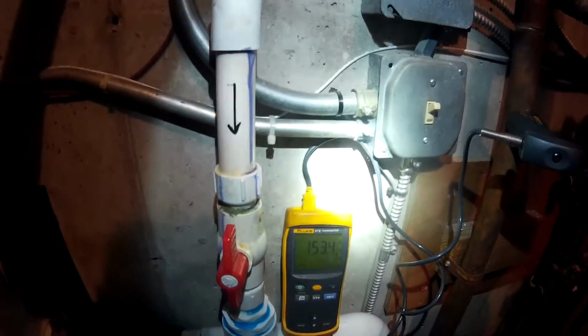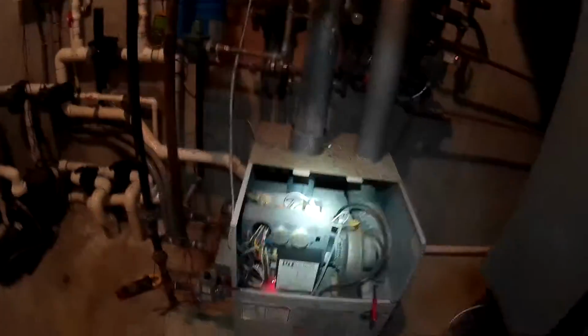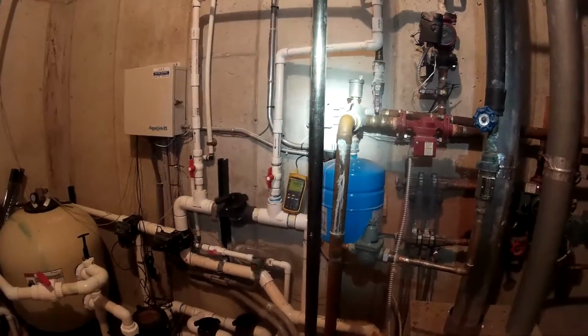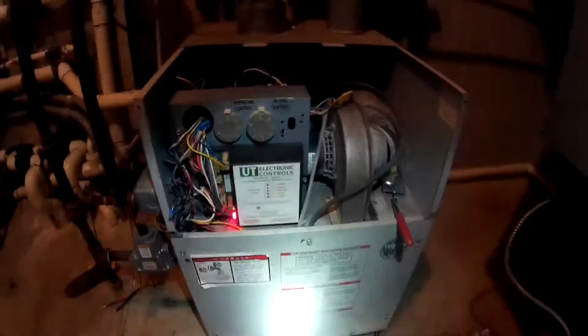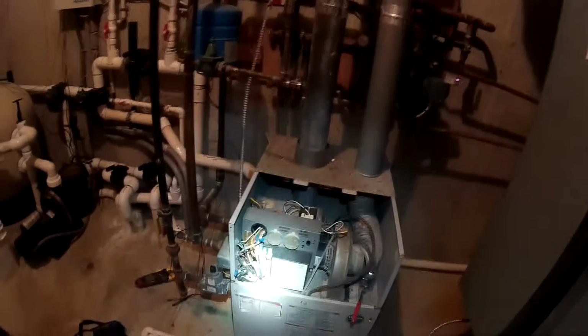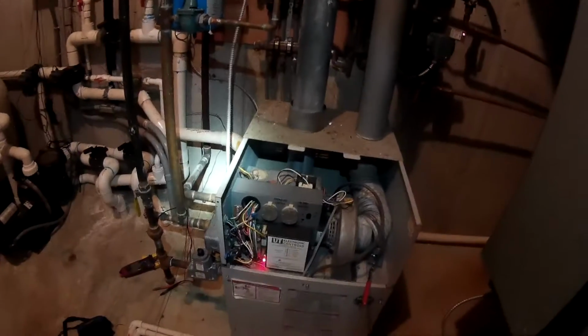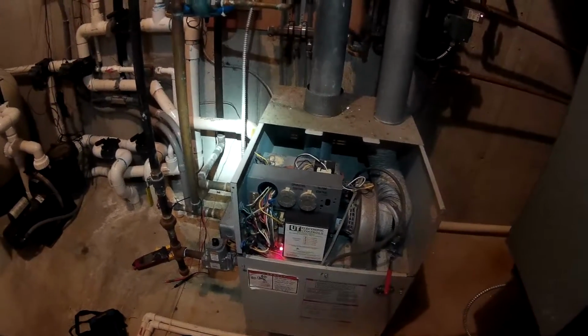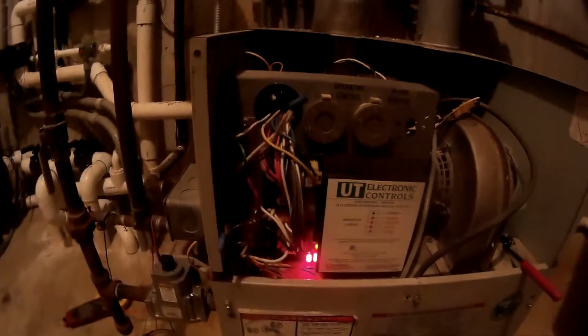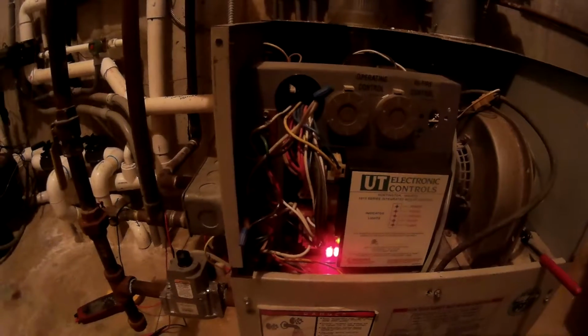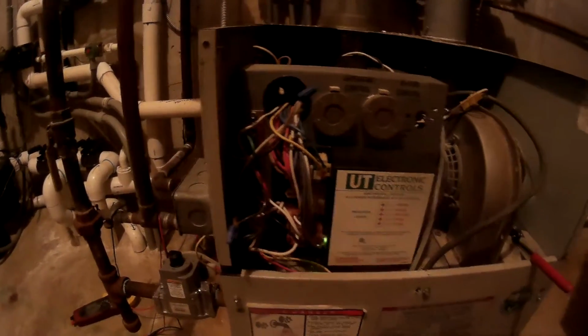So last time we shut off at 200 degrees just by tapping the control. So 150, 160. And our gauge is sticking. Still firing. 168, still firing. I'm set for 140. That is 179, 180, still firing. This time I shut off at 189. So just by tapping the control I got it to work, but it's dangerous to operate. You can't operate like that.